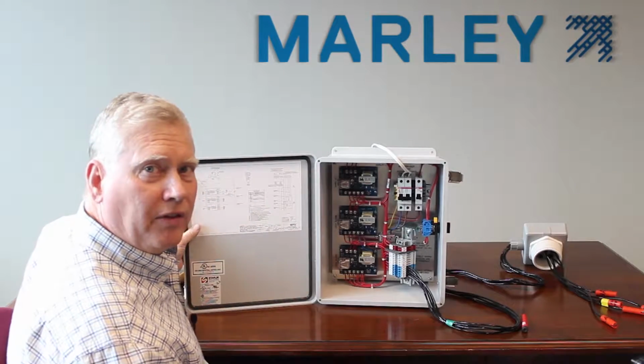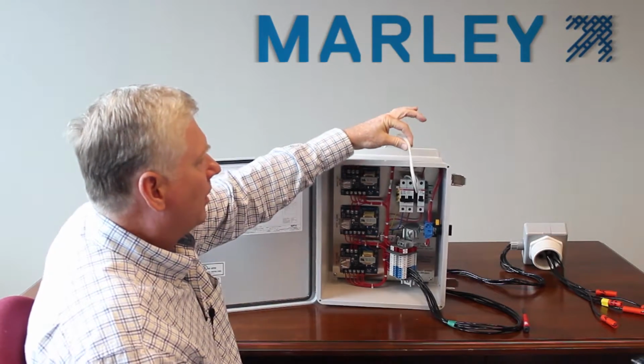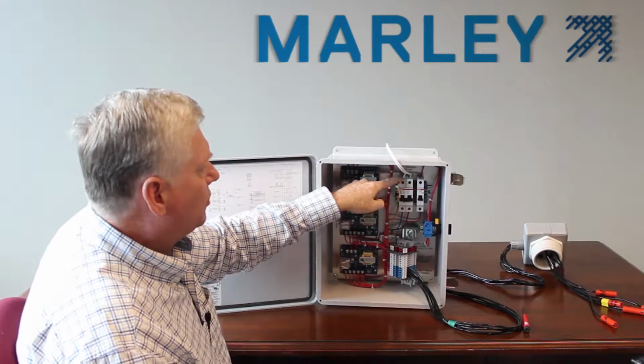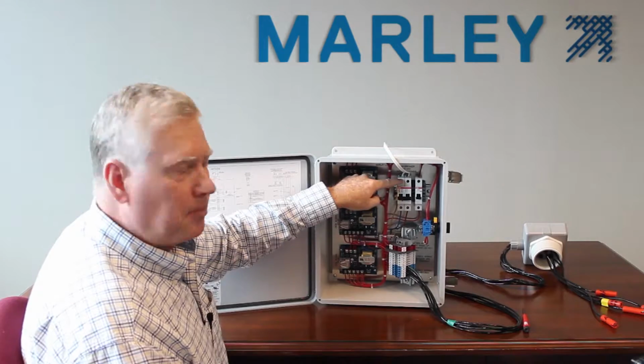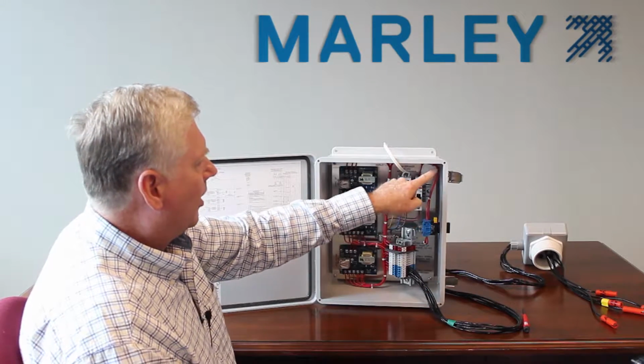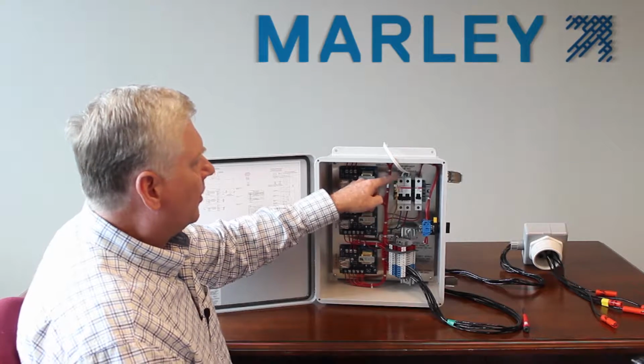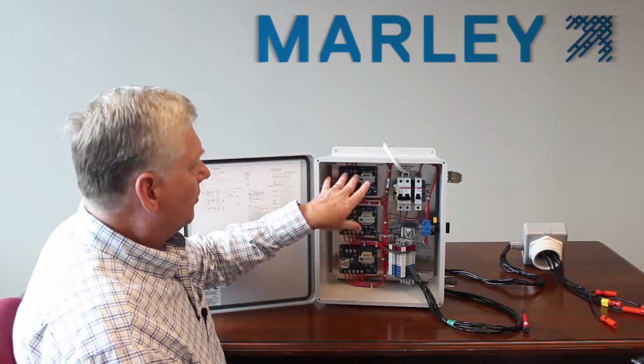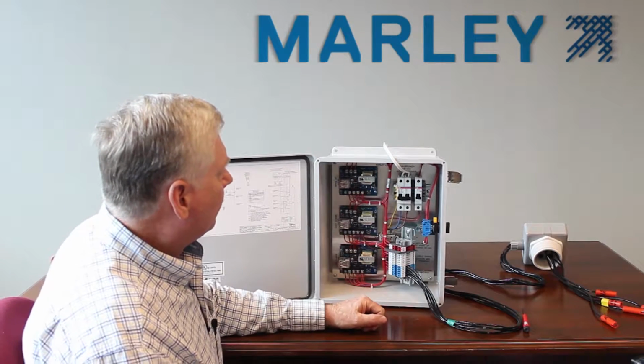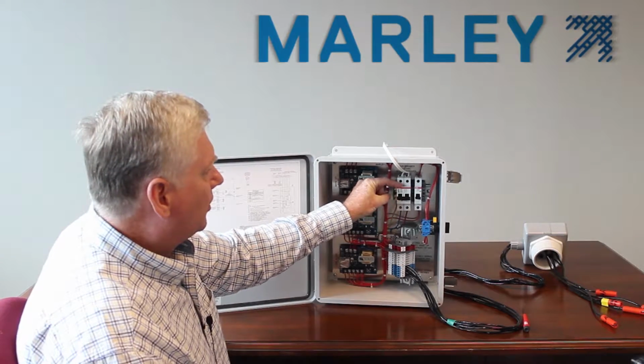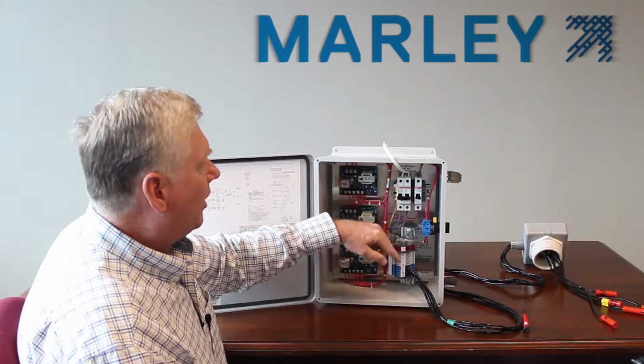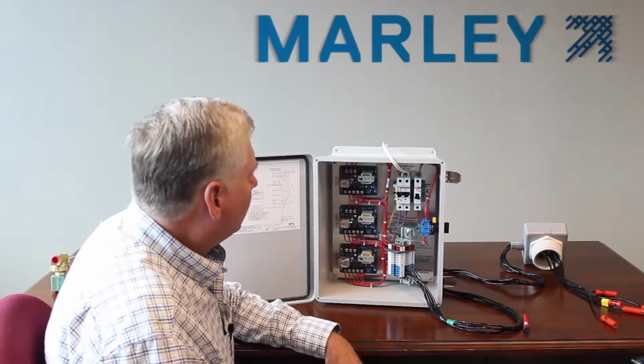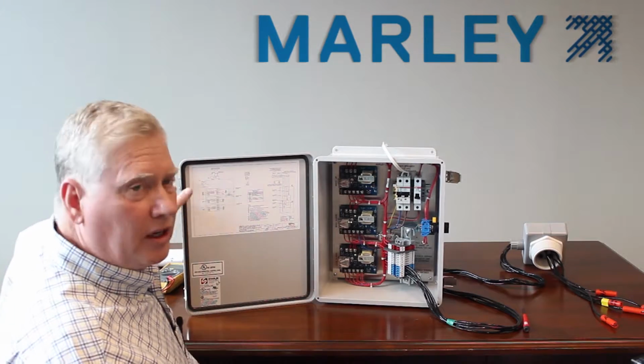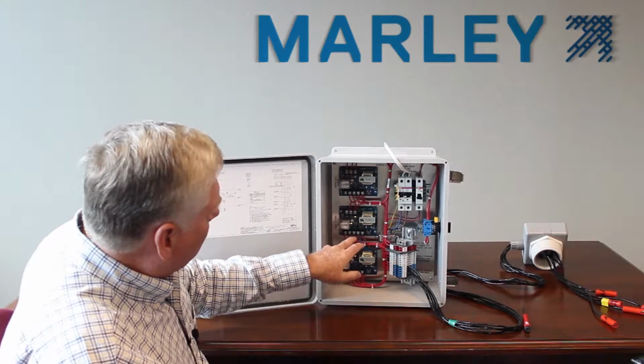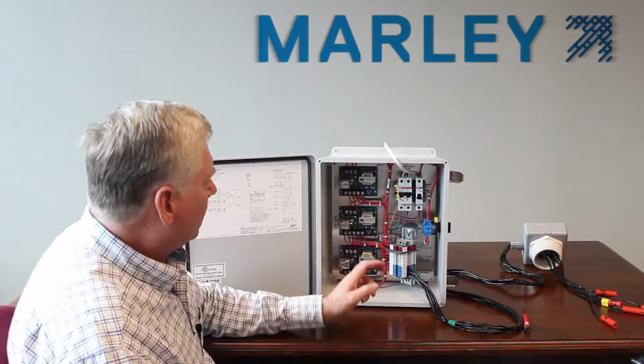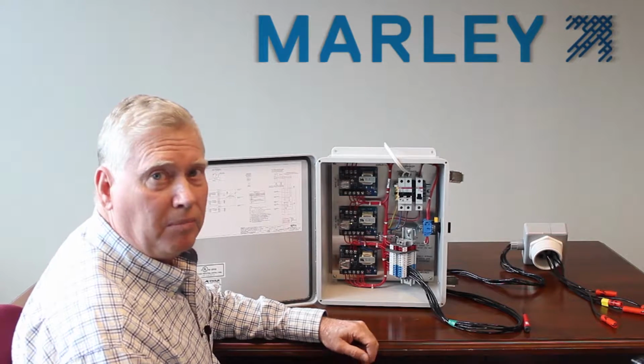So I have a real control panel here on the desk, and I ran 120 volt power to the main circuit breaker. This is called the line side of the breaker. Typically out in the field, your wiring is going to come up from the bottom, up and over and into the top of this main breaker. Once power runs through the main breaker, it's distributed throughout all the circuit cards. So you have to have the circuit breaker in the on position. With most circuit breakers, with the handle down, you're in the off position. You flip it up, now we're powered on, and you'll see some lights come on the cards. That's telling you that the cards are energized, they are receiving power.